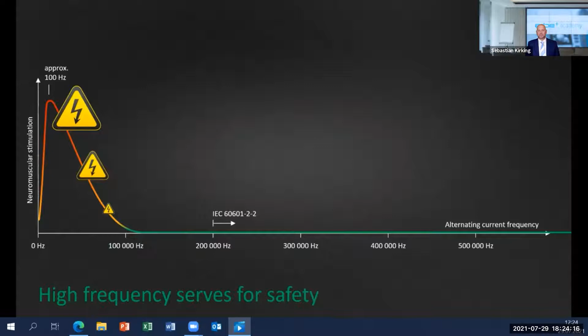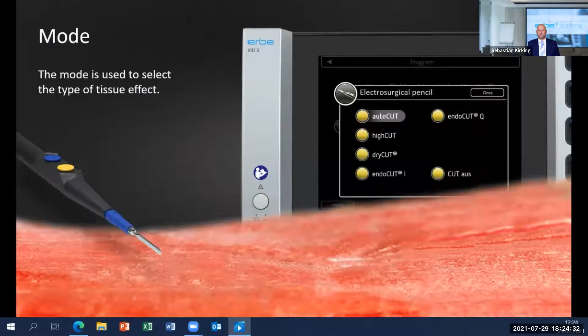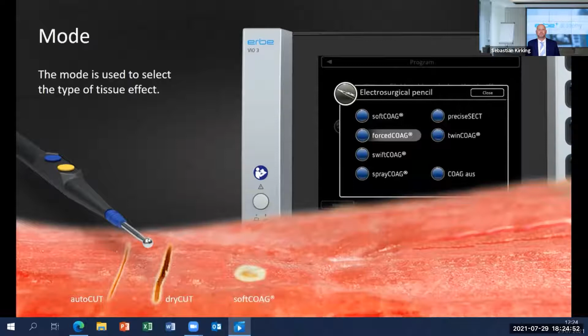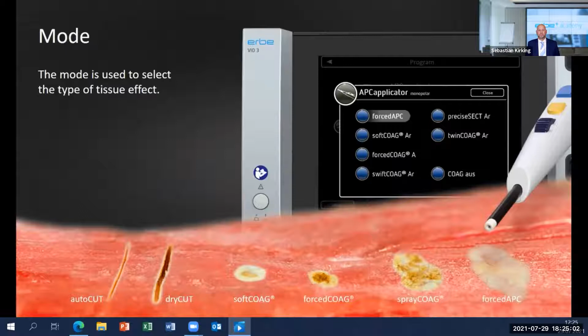Typically, electrosurgical units have so-called modes to select from. With the mode, you basically select a certain type of tissue effect. The yellow button activates rather sharp cutting modes like auto cut, or sort of a blended cut with an intensive coagulation seam like the dry cut. The blue button activates coagulation modes like soft coag that will produce a sort of boiling effect, or forced coag that will make a rather fast and dry coagulation. Spray coag, and especially argon plasma coagulation, will produce longer sparks that can be used for fast and broad coagulation with less penetration depth.